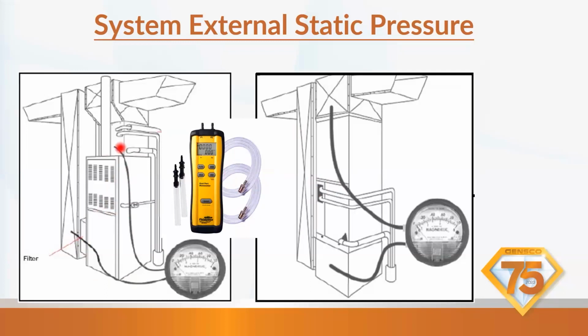So in this evaporator coil, we want to be in the A, because that A coil is going to be like this. We have to be below the A coil. We can't be up here in the supply, because we want to just test our external static pressure over the furnace. We can take another reading across the coil to see what kind of pressure drop we have across that. But when taking static pressure to see if we're moving the correct amount and that we're breathing correctly, this is where we're going to take it.